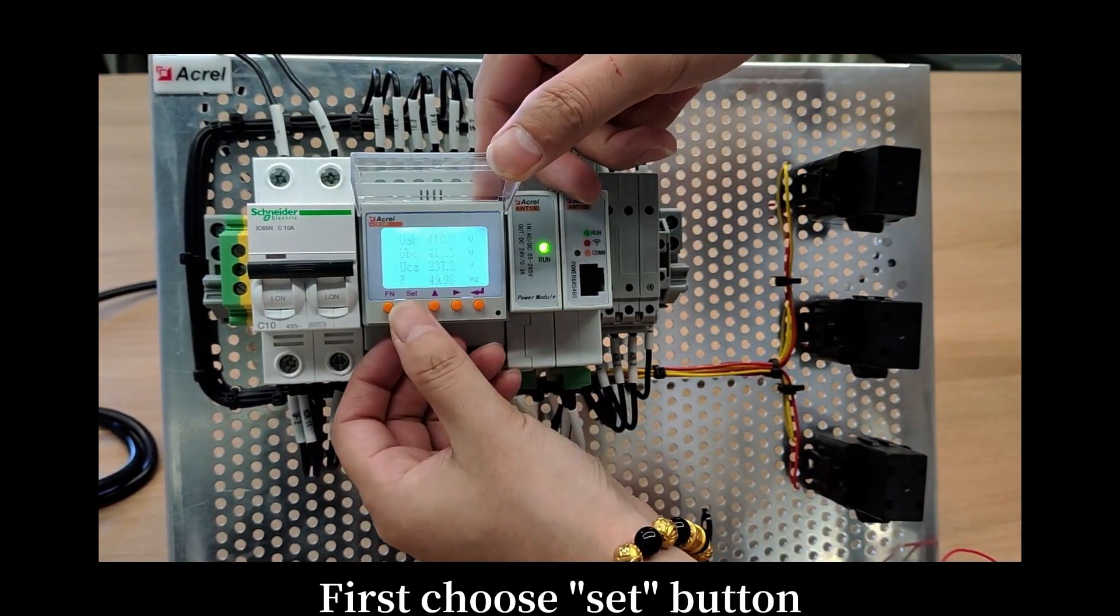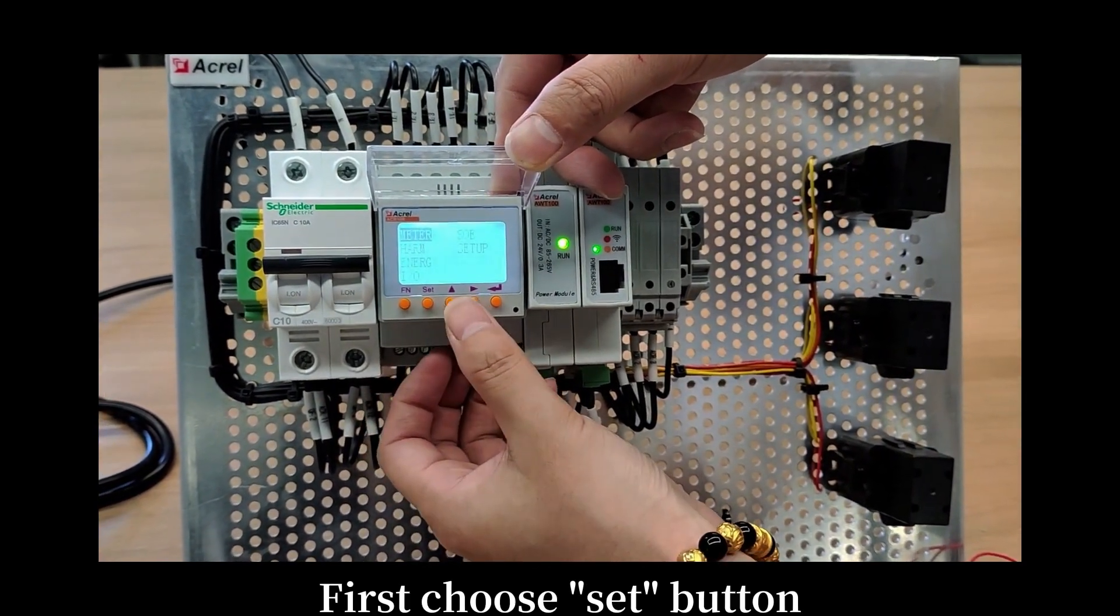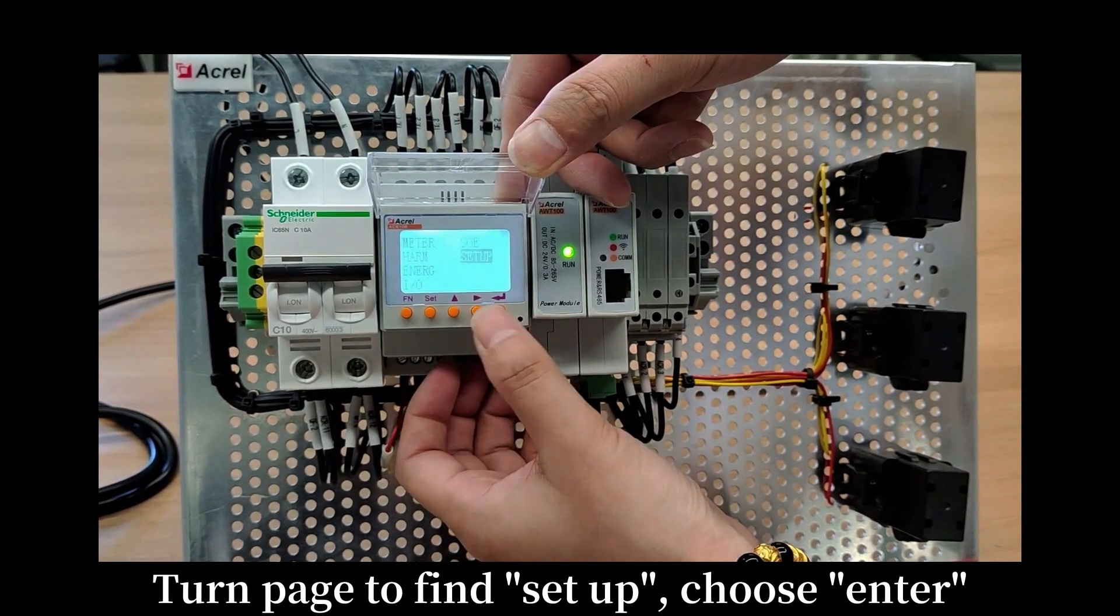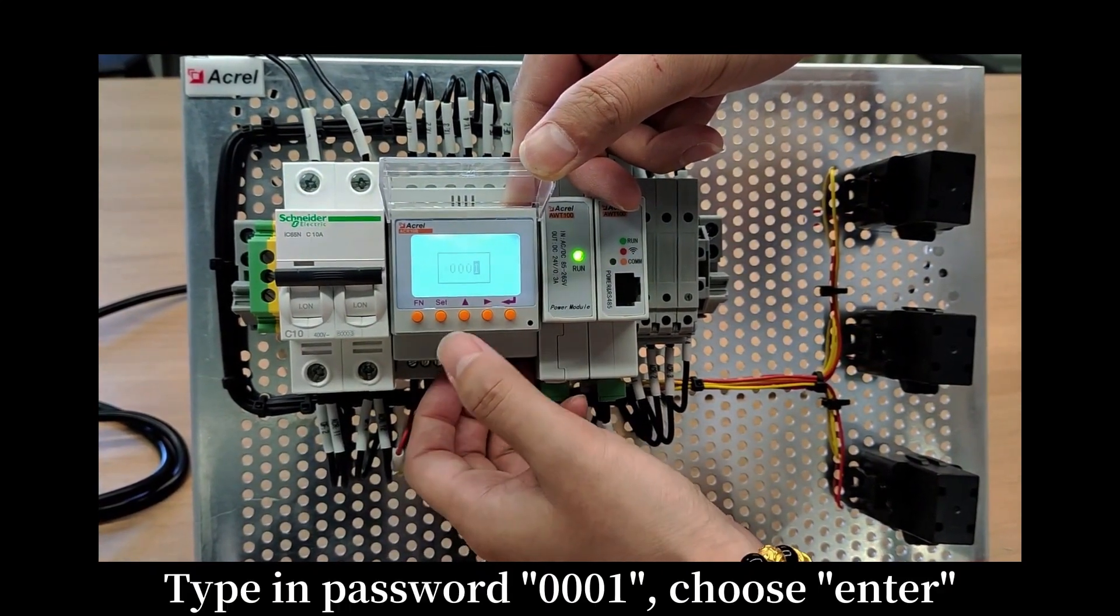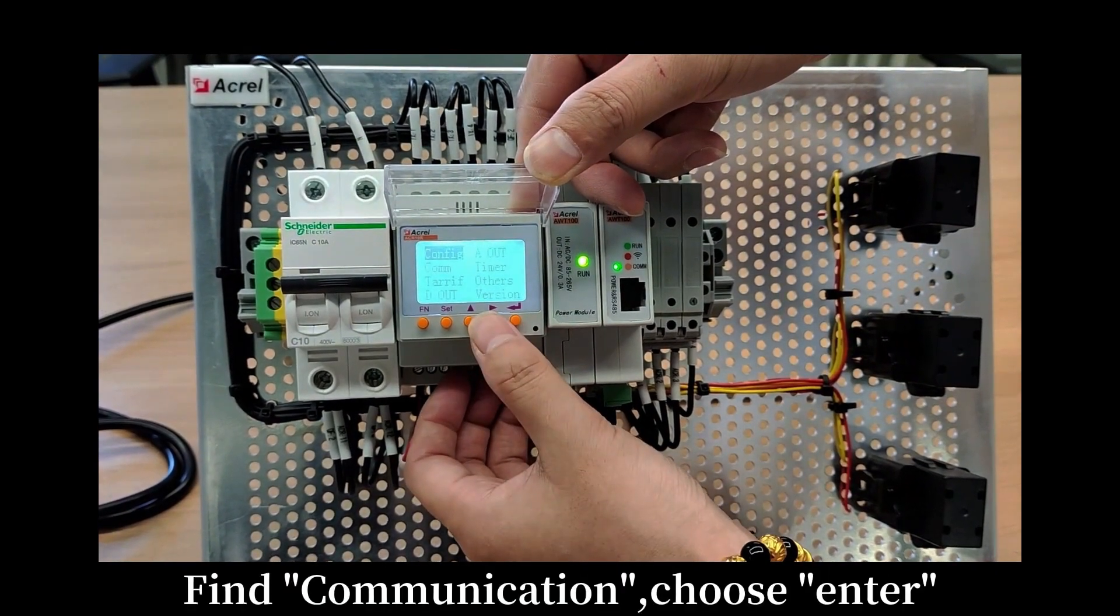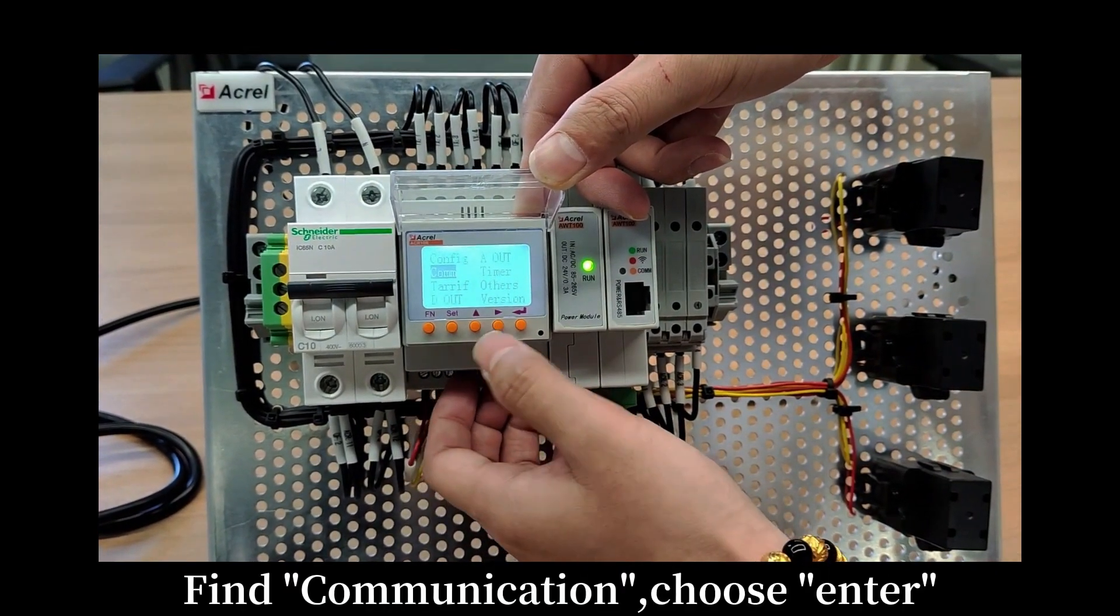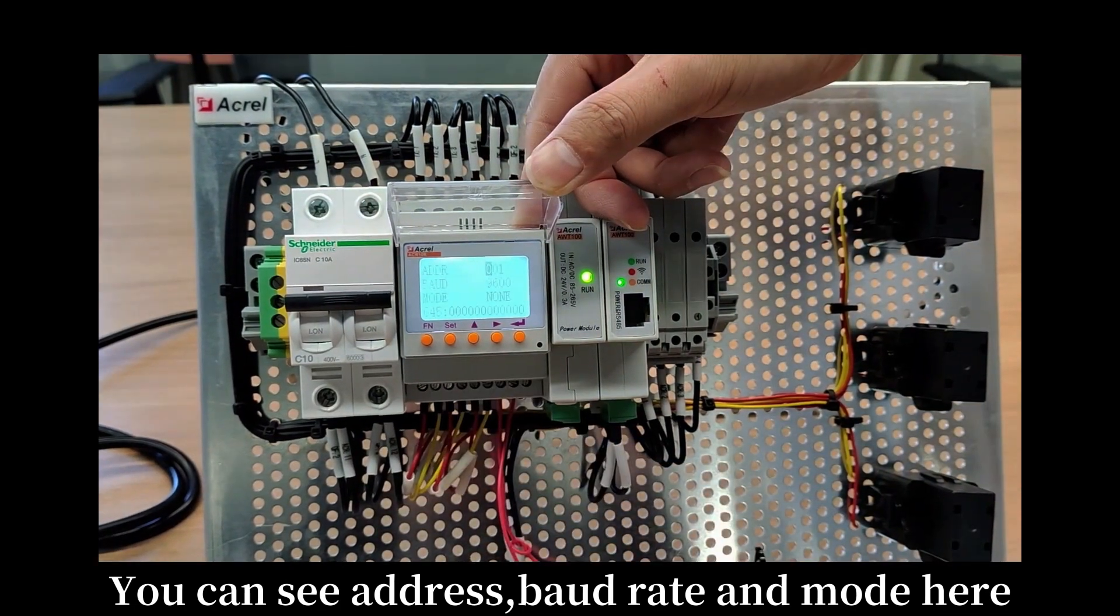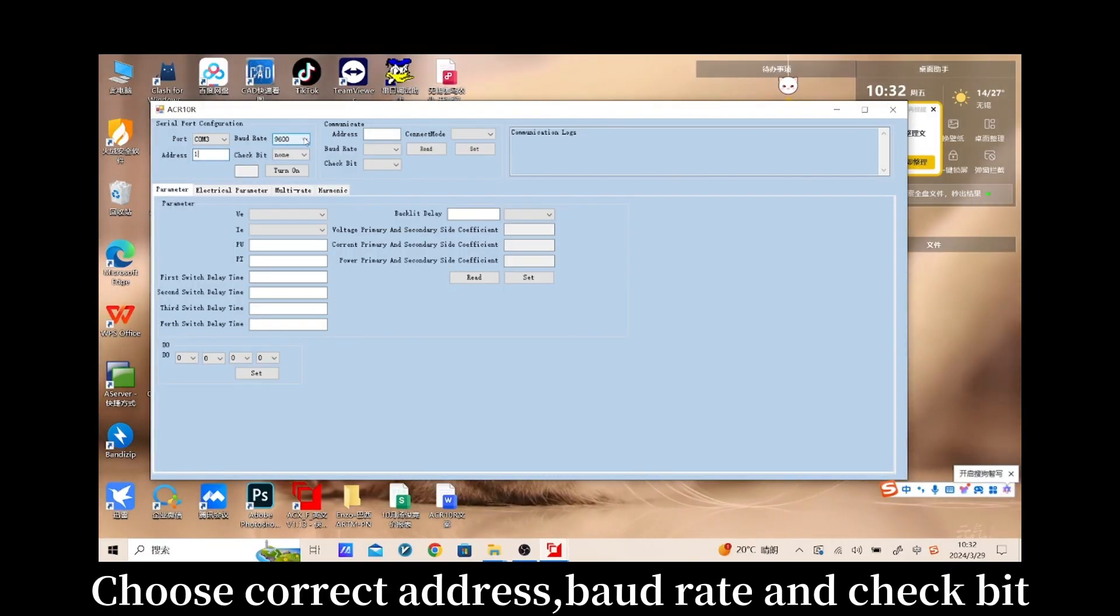First, choose set button. Turn page and find setup. Choose enter. Type in password 0001. Choose enter. Find communication. Choose enter. You can see address, baud rate and mode here. Choose correct address, baud rate and check bit.